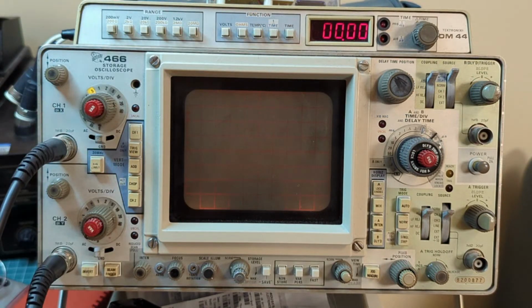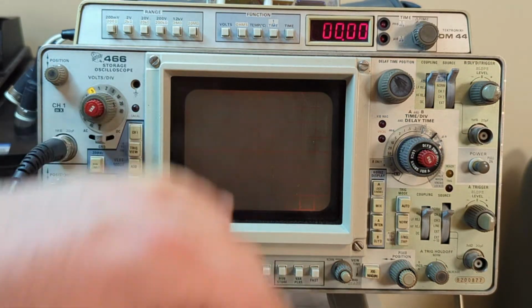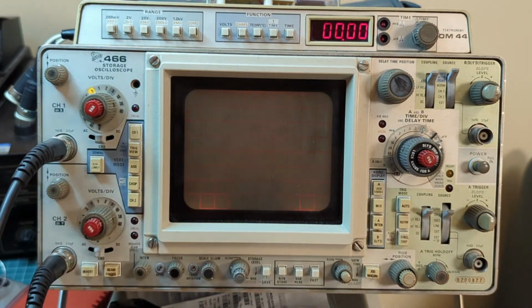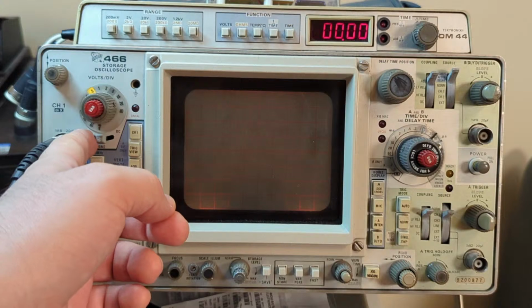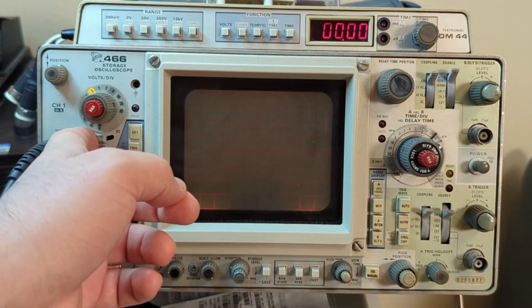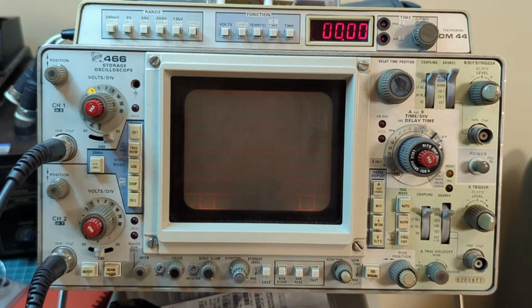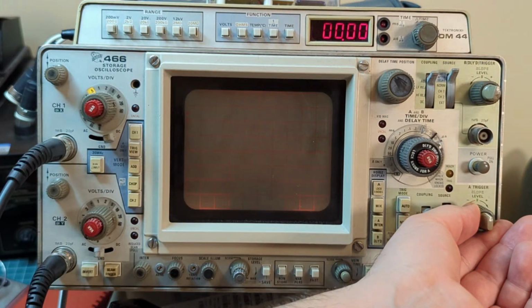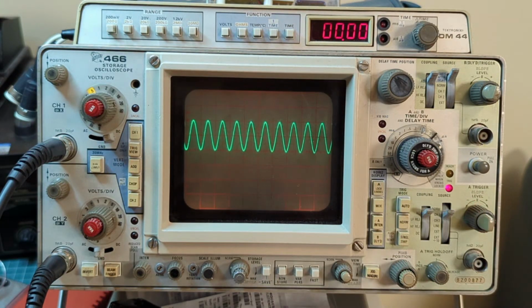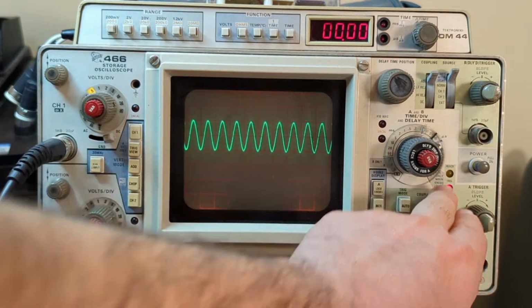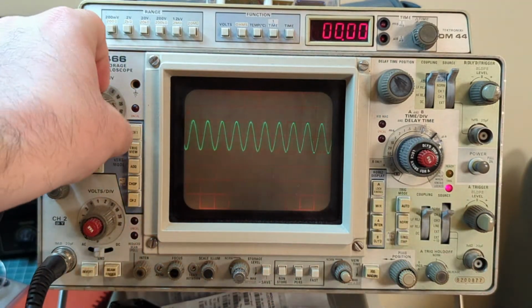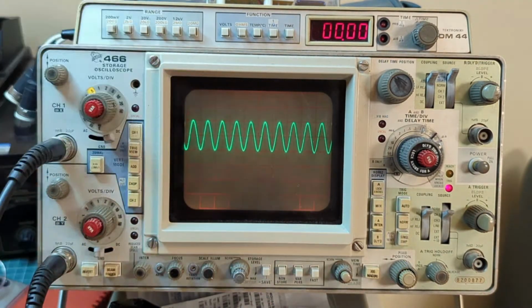So if you only want to have a triggered sweep, then you use the normal mode. And as you can see, the trace is out because we are not triggered. So we can trigger it once again by going to DC coupling and by adjusting the trigger level properly. And now, as you can see, once we are triggered, we get a trace. If you lose the trigger, you lose the trace. That's what normal mode means.